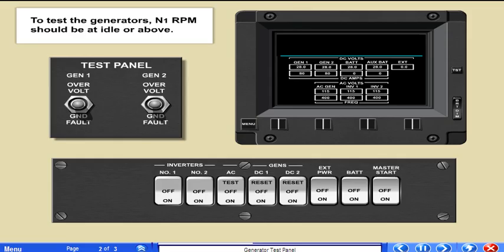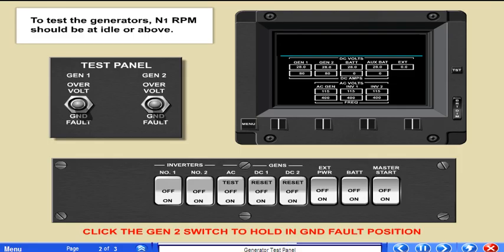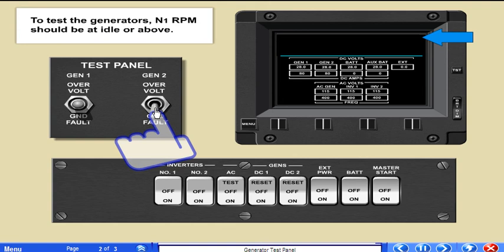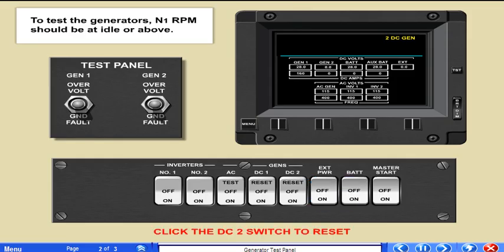When either switch is held to the ground fault position for 5 seconds, the associated DC generator message should illuminate because the generator is now offline. Reset the generator by selecting Reset on the generator switch and then to the on position.